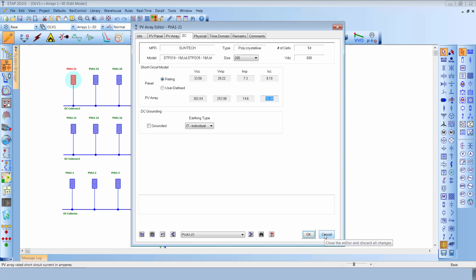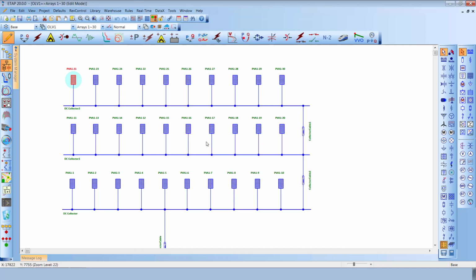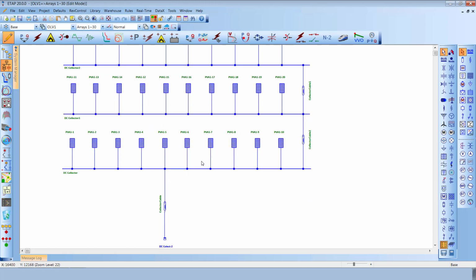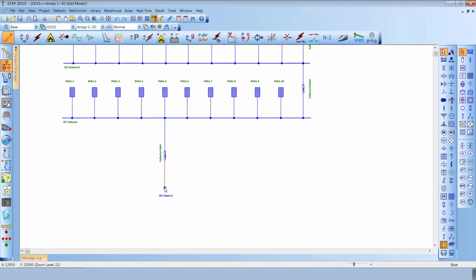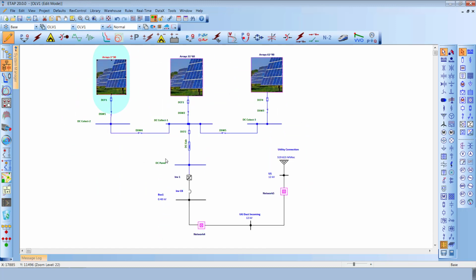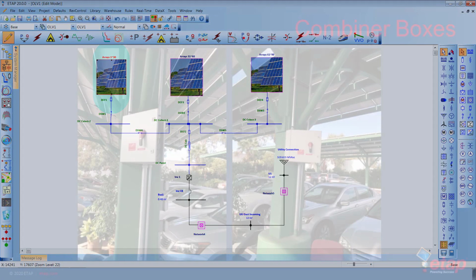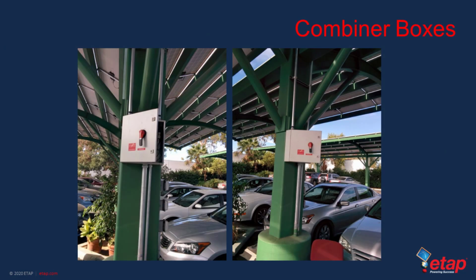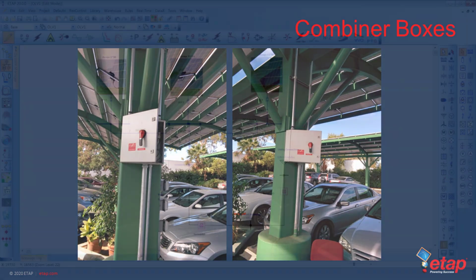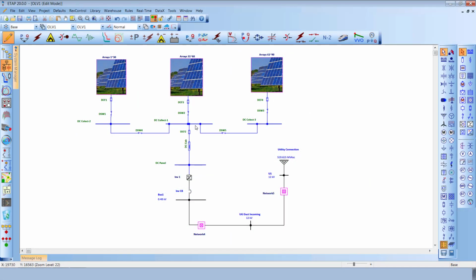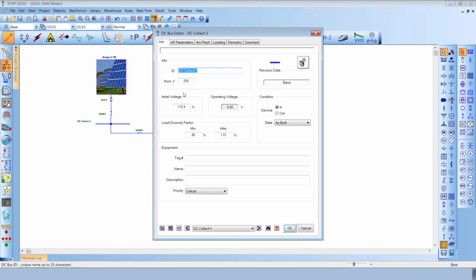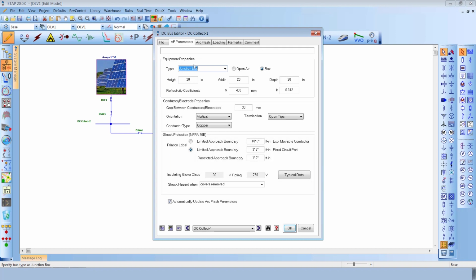Once this is done, the next step is to model the combiner box fed from these PV panels through a collector cable, as shown in this picture. The DC collector systems or combiner boxes can be modeled in the bus editor, starting with the nominal voltage in DC and then the corresponding arc flash parameters listed in the equipment properties section.